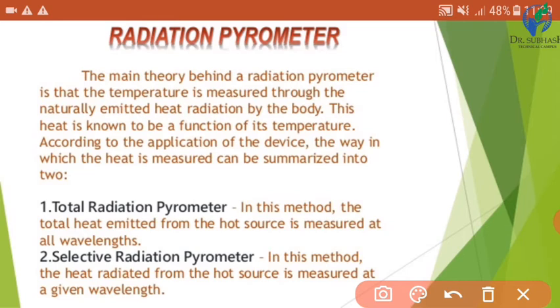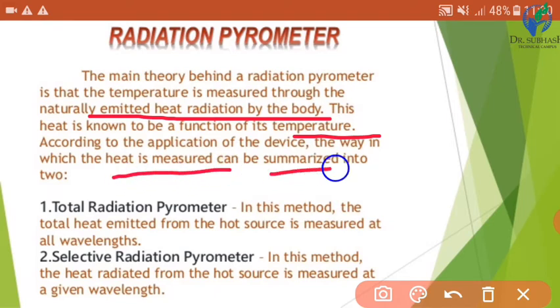Now, the main theory behind the radiation pyrometer is that the temperature is measured through the naturally emitted heat radiation by the body that we have already seen. This heat is known to be a function of its temperature. So, heat radiation is directly proportional to temperature. It means if there is a change in temperature, then the radiation will change. Okay. So, according to the application of the device, the way in which the heat is measured can be summarized into two categories. One is the total radiation pyrometer.